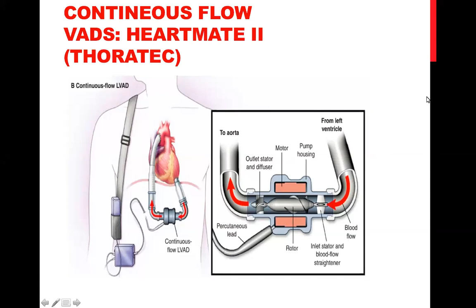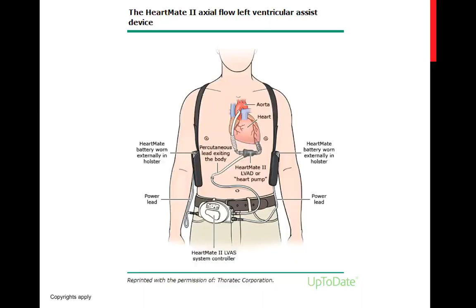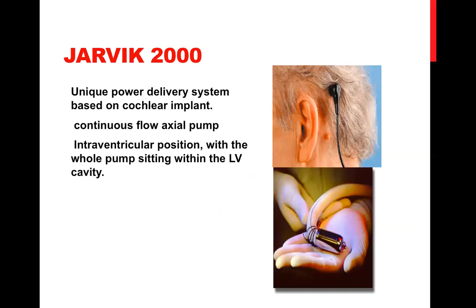It was an excellent device despite the fact that it was a pulsatile device, but it had an excellent outcome in comparison to NovaCor and the other pulsatile extracorporeal device that was coming from THORATEC. Continue, please. Okay. This is just another picture of the HEARTMATE 2. Okay, here comes the Jarvik 2000. It has a unique power delivery system based on a cochlear implant, and it's a continuous flow axial pump, and it was in an intraventricular position with the whole pump sitting within the LV cavity.